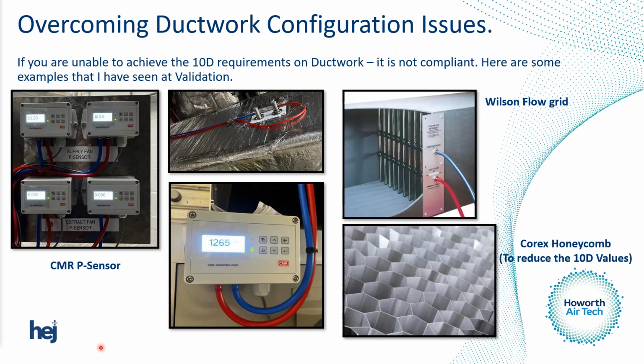And these are some examples that I've seen whilst I've been out on site. This is a CMRP sensor. They're not very popular, but there are quite a few of them out in the industry. Basically the way that they work is they sit on the air handling unit somewhere, and you can see these lances that sit inside the ductwork, measure a pressure, and turn that into a velocity. So you can see this reading out here is 1.265 cubic metres per second, or 1,265 litres flowing through it.